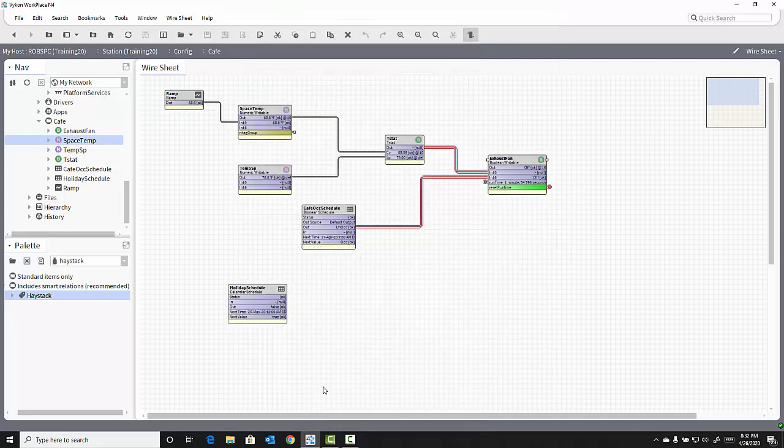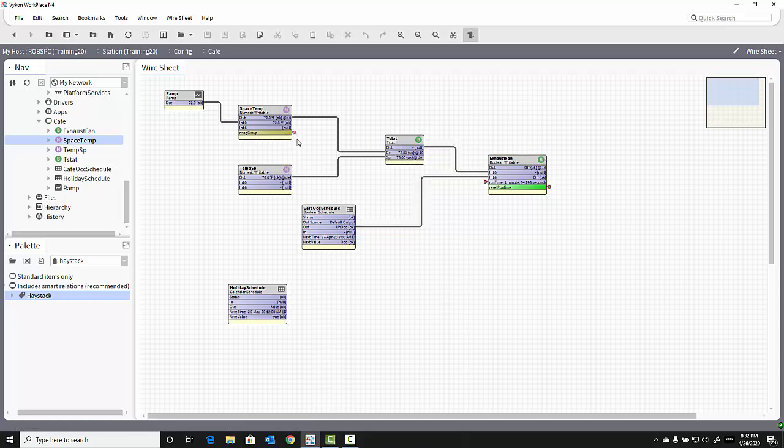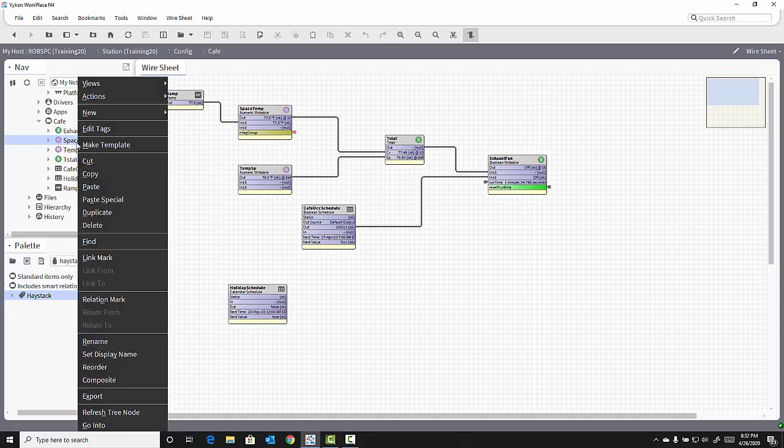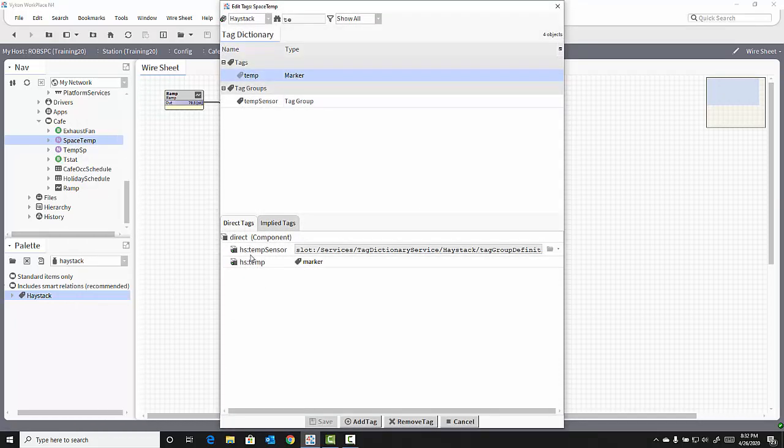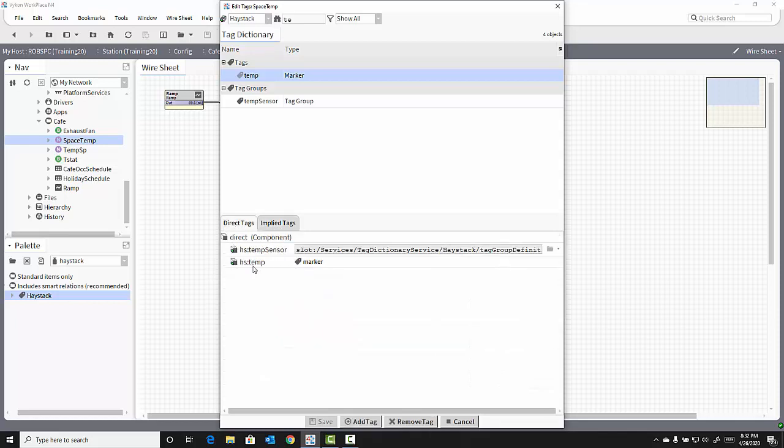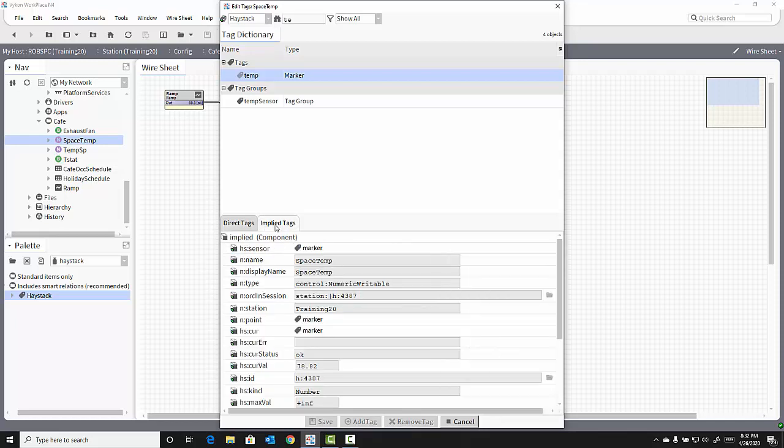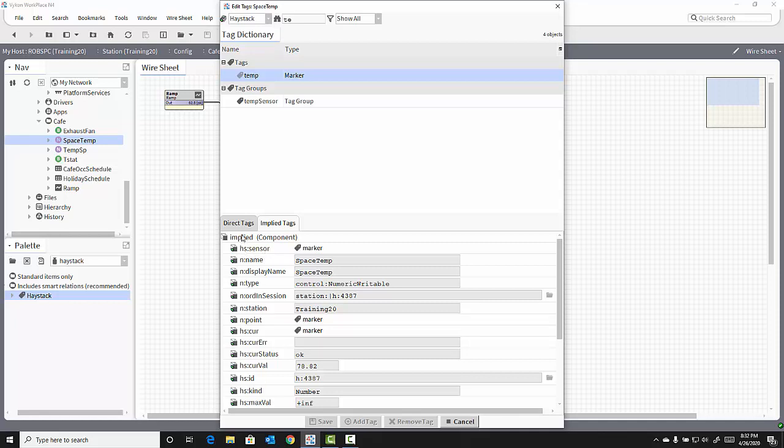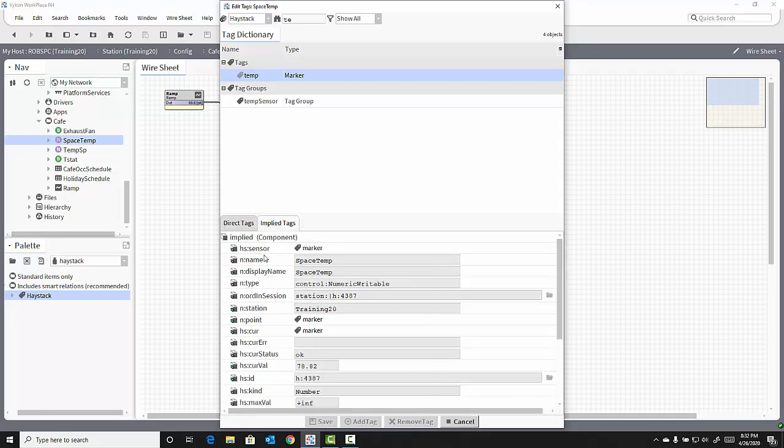When you add a tag group, on your wire sheet, you may see a link to that tag group appear. You do not see that link for individual tags. If I look at my space temp object again and click Edit Tags, I see that both of those tags are added to the space temp, the temp and the temp sensor tag. But if I look at the implied tags, in addition to temperature, the temp sensor tag includes the HS sensor tag as part of that tag group, making this point searchable by both temp and sensor.